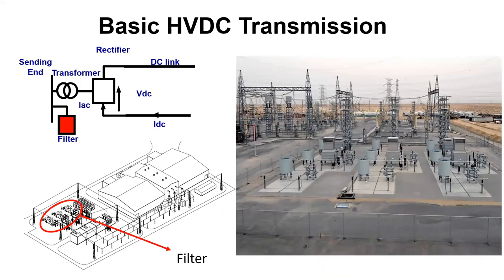The next slide shows a typical filter yard, which is definitely required with LCC. It is one of the main reasons for an LCC station being bigger in footprint than a VSC station. You can see this from this picture. It shows a reactor, which are these cylindrical coils, resistors, which are these boxes, and capacitor units. This particular picture shows three levels of combination of resistor, reactor and capacitor, and therefore it is a picture of a triple tuned filter. If there were two levels, it would be a double tuned filter, and if there was a single level, it would be a single tuned filter.